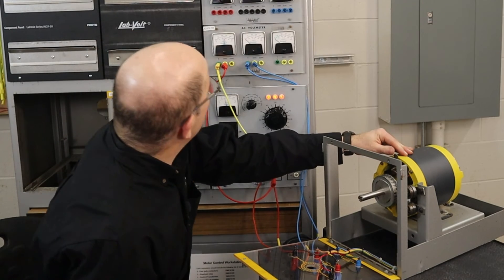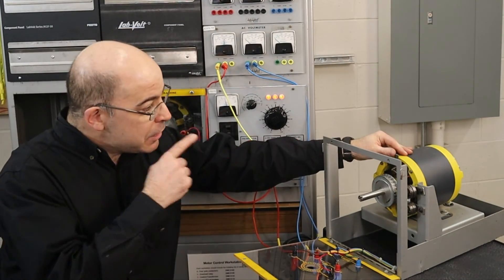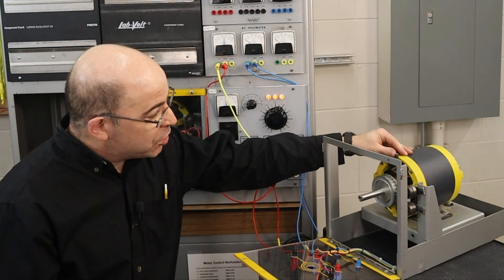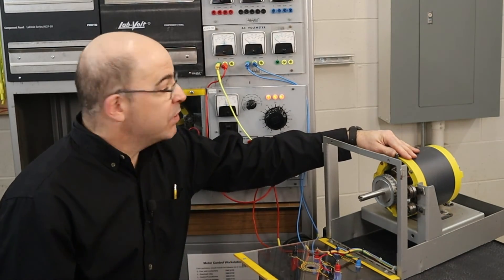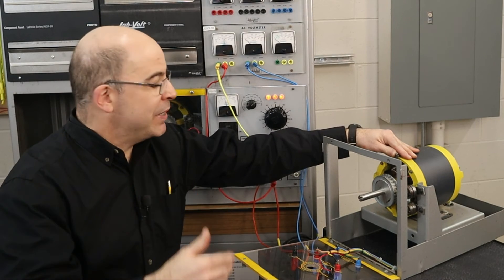See right about there I'm almost at zero, but now if I continue to push this lever or the yoke that adjusts my brushes, if I continue to go past this point what we should see is that the voltage is starting to increase again.